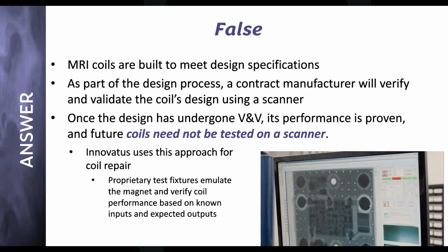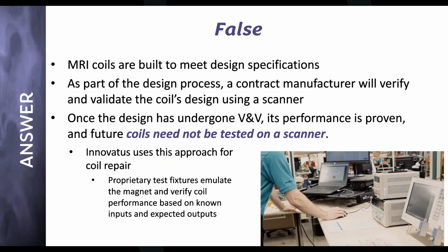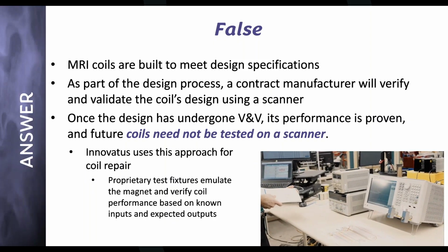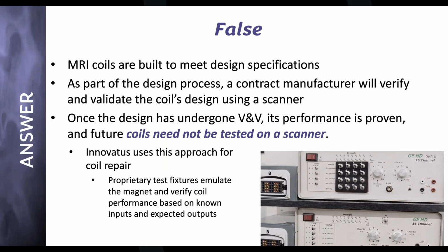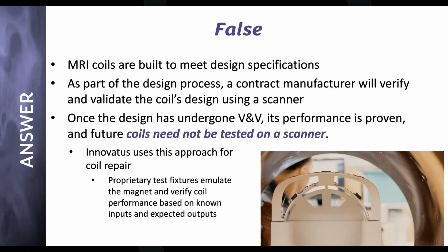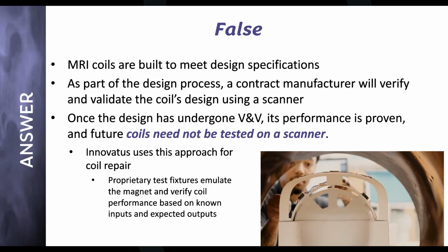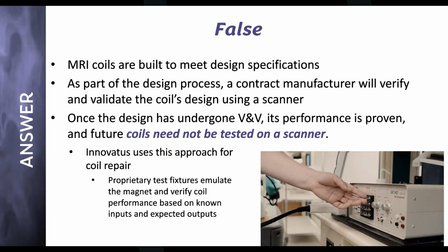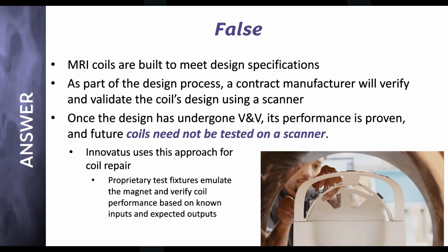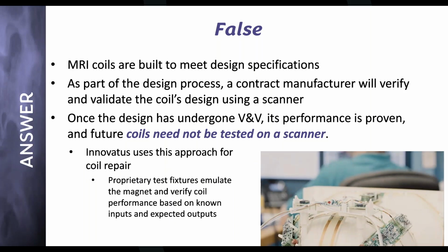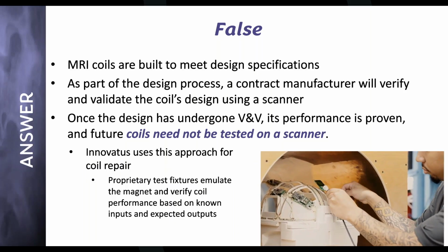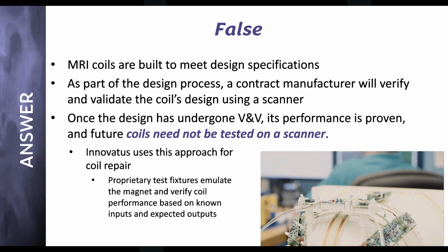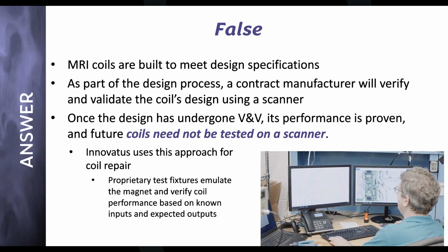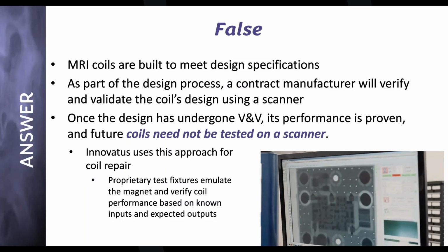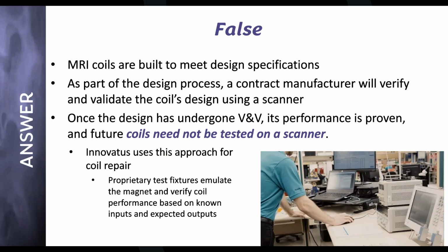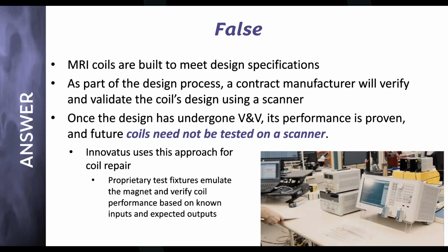There's claims out there where people say they test every single coil they repair with a test bed. That's impossible. We do over 1,000 different coils. We probably would have to have 100 different magnets, and a magnet is what, $500,000, give or take, some up into $1 million. And not to mention the power you would have to have in your facility to power 100 magnets, it's basically the grid of a small town. So it would make the repair just financially unstable. It wouldn't make any sense to repair something. So nobody can test a coil repair on every single coil. And so these emulators allow us to do that.